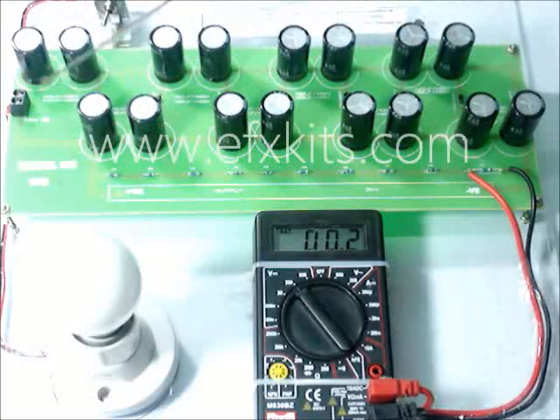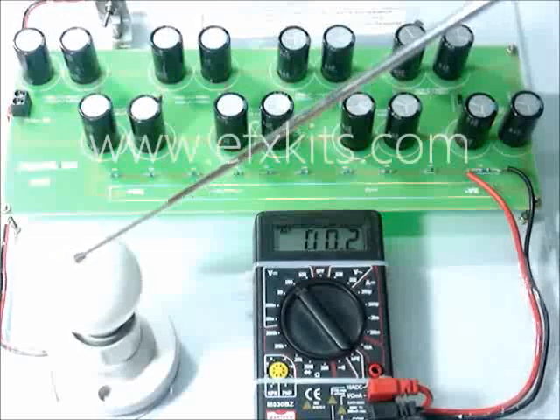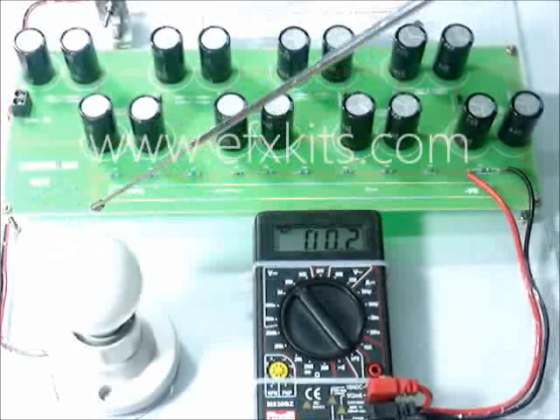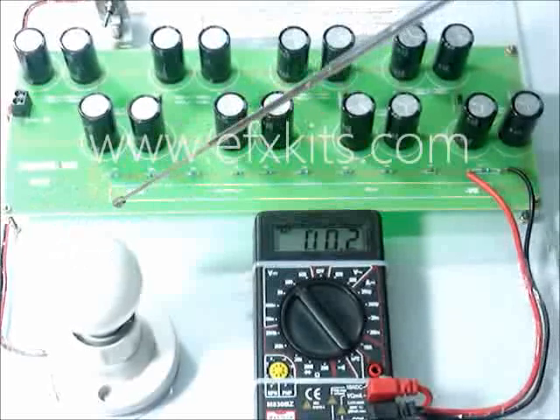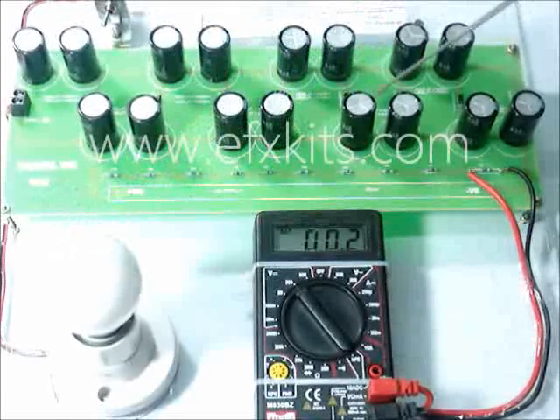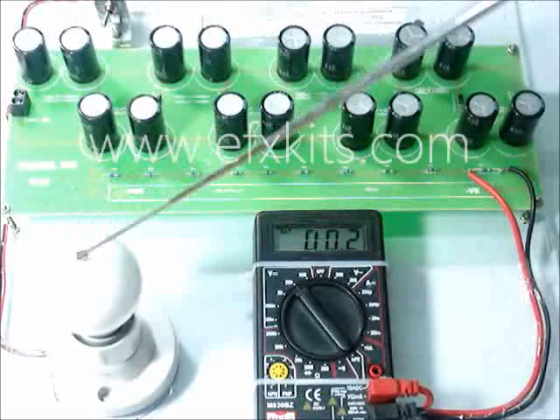Instead of applying 230 volts directly, we apply it through a series lamp so that the starting current is controlled. Otherwise, the starting current would be very high because of the large number of capacitors. That's why we have a lamp here as well.